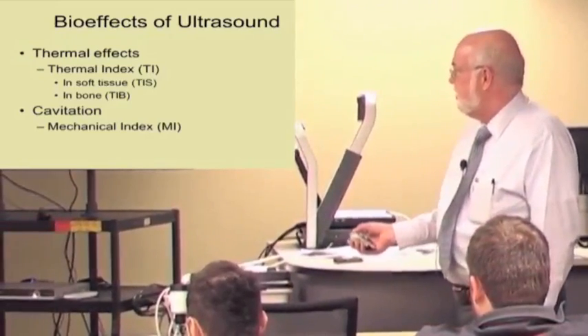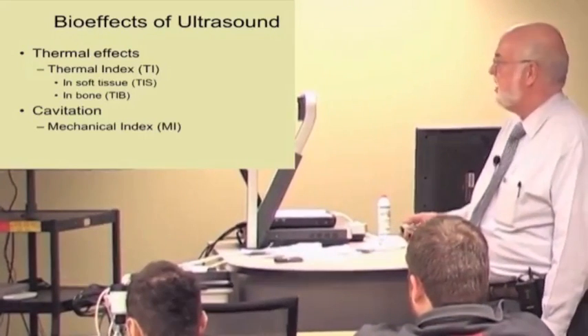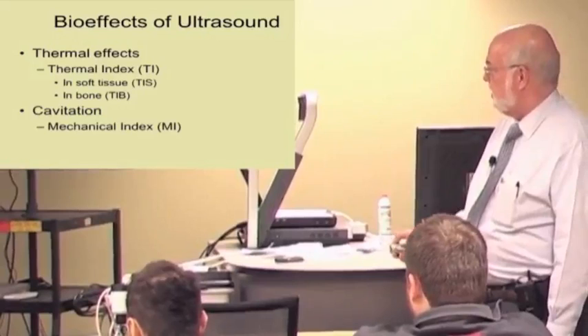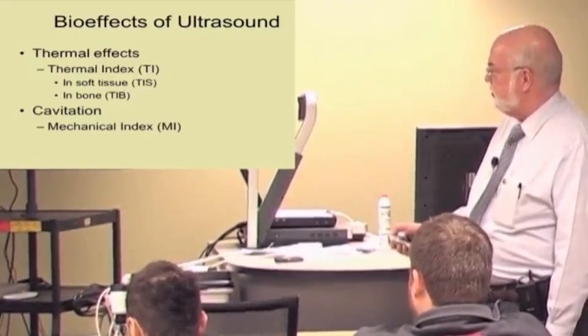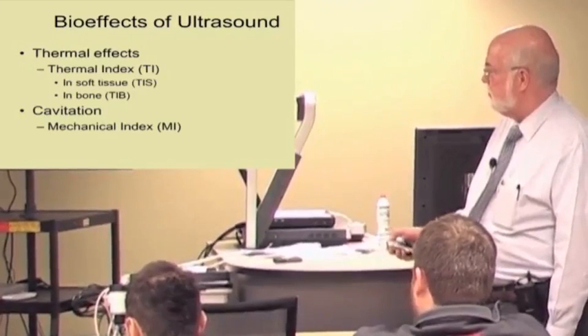In the last several years, there's been a requirement from the FDA that all diagnostic ultrasound equipment has to display a thermal index and a mechanical index. The thermal effects, sometimes you'll see it as TIS, which is thermal index in soft tissue, or TIB, thermal index in bone.